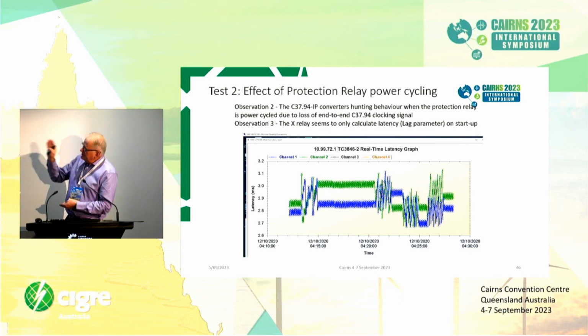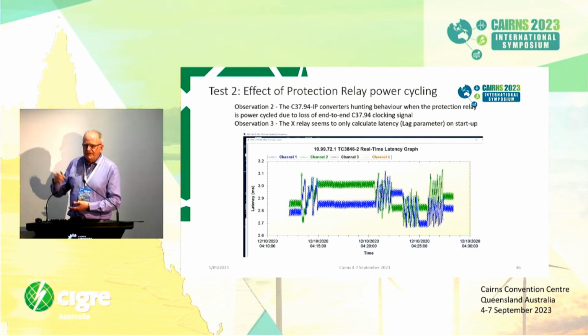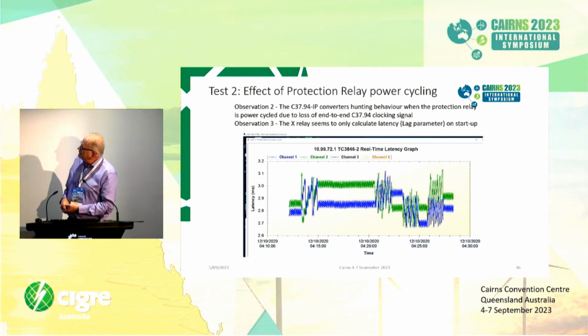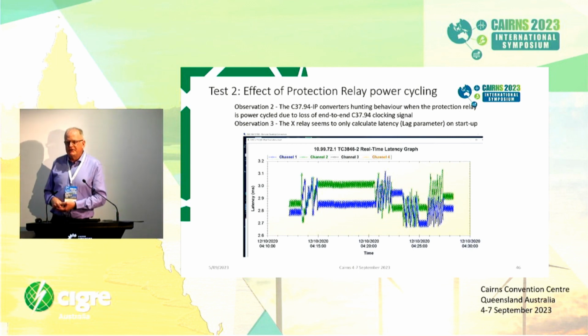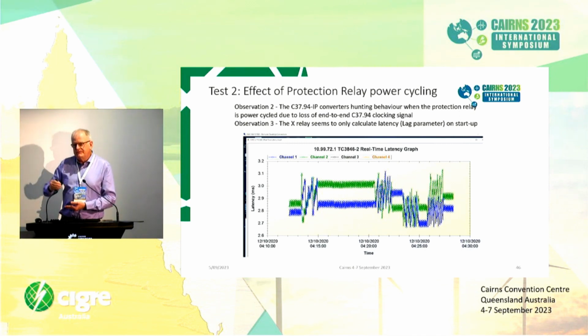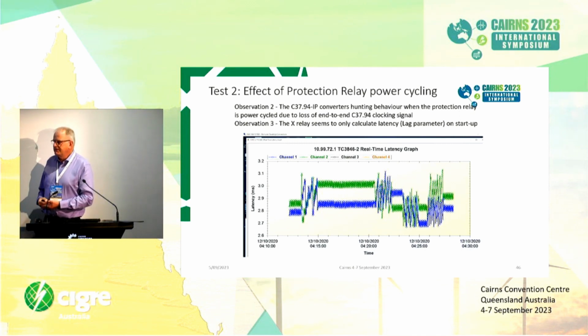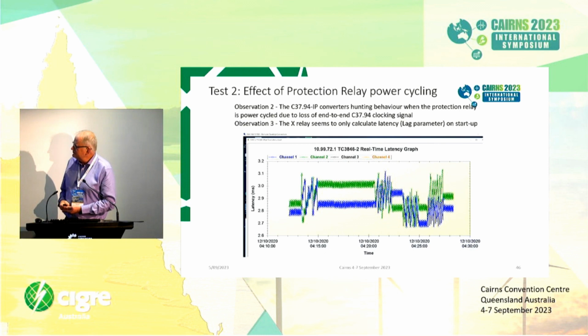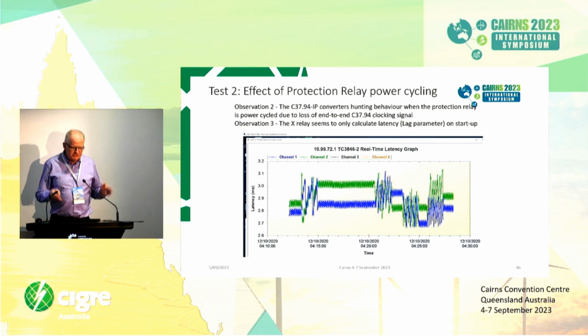But once the communications comes back again, once the protection relays are turned back on and you get that loop back, the actual system settles down again and becomes stable. But interestingly, it becomes stable at a different latency figure. So that's one reason why we saw a bit of a jump in the round trip time latencies and the ping pong method calculations during each part of this particular test. I would say that's an observation.